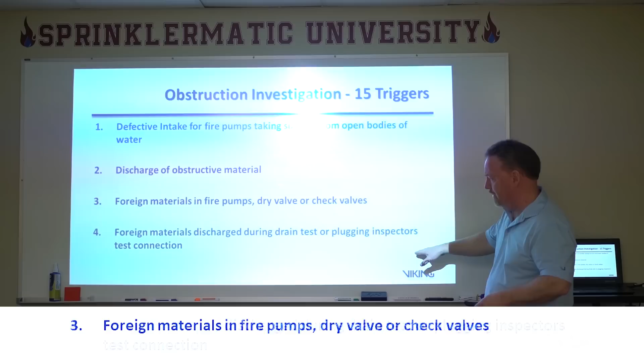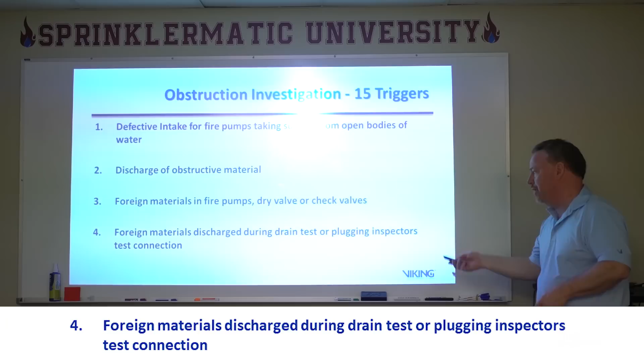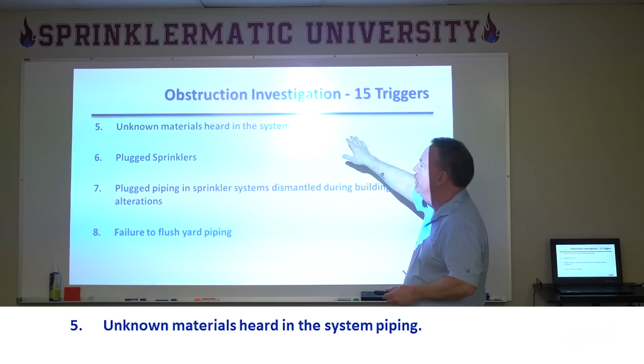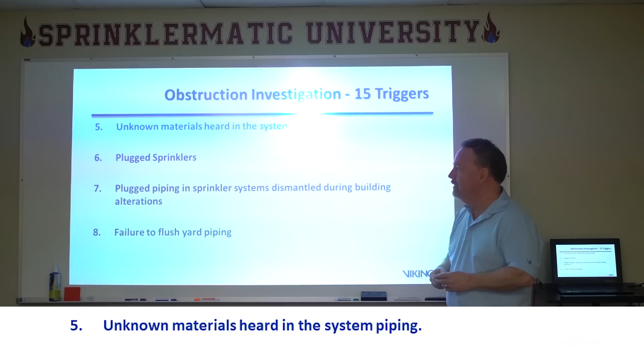You're going to do an obstruction investigation for any foreign materials anywhere in the system. Basically these three could be combined together: foreign materials anywhere in the system, discharge during a drain, discharge anywhere. Also, unknown material heard in the system piping. Even if you're hearing it rattling down the main, you want to make sure that's going to be a trigger.